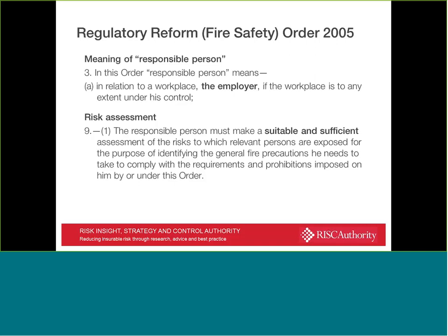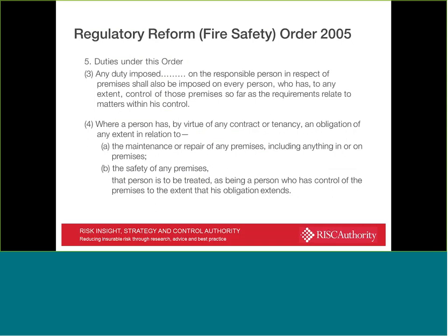Now, of course, I'm dealing with a piece of legislation that's only applicable in England and Wales. Scotland and Northern Ireland all have their own legislation, but the requirements are all very, very similar. In general terms, there's a requirement to make a suitable and sufficient assessment of the risks to which people are exposed, and of course if they don't consider the risks associated with the extract ductwork and the potential for fire to spread into and beyond the ductwork, then the assessment could be deemed as not being suitable and sufficient. I'm sure that's the way enforcing authorities would look at it.